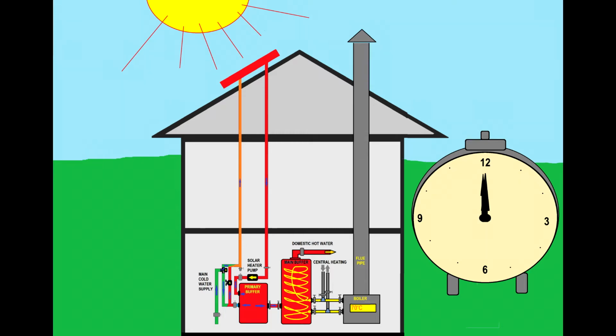Then if the water usage increases, the primary buffer and the solar panel, through the ring circuit, might have the capability to compensate for a lot of water displaced by the fresh water, by the consumption of the domestic hot water. So the main cold water supply will push water into the system, which is cold and will mix with the hot water of the pre-buffer, but that water will be pushed first through the solar heater panel. And water from the primary tank will migrate into this main buffer tank. And this is the point where you will save a lot of energy.